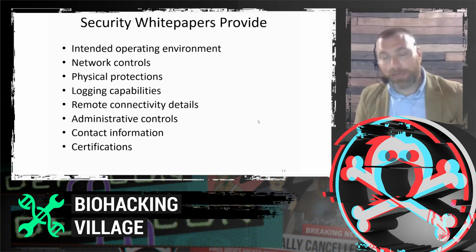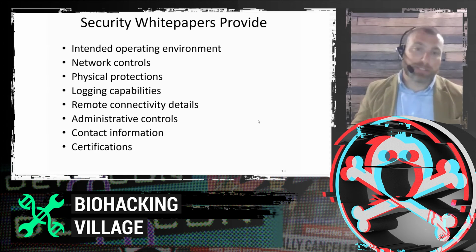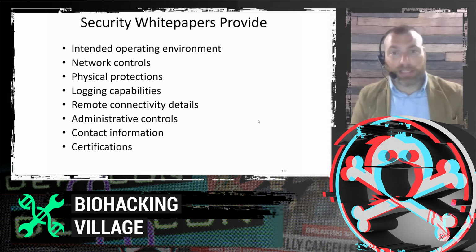The intended operating environment is important because, again, going back to those manufacturer assumptions, this is where the manufacturer assumes the device is going to live. So they assume that there's going to be network segmentation and a firewall and a number of other things.